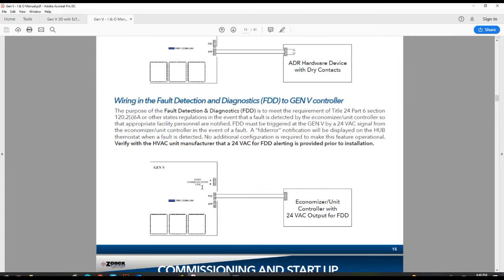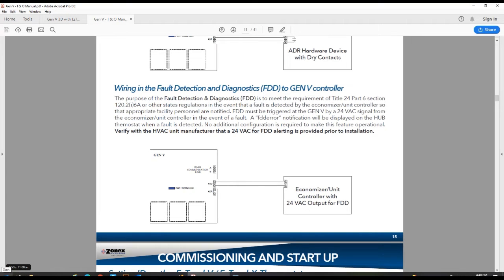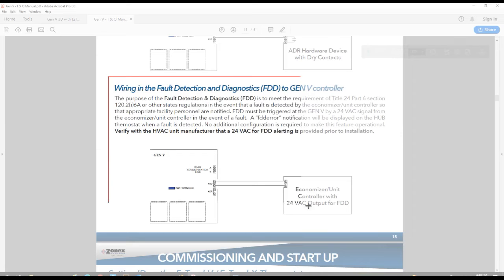We also have what's called FDD. This is the fault detection diagnostic feature. This terminal allows you to hook up an economizer to our controller that offers the FDD output or input. When your economizer has failed or there's an issue with it, it will send a signal to our controller. Then in turn, our controller will put an error message on your hub thermostat saying FDD error, and that is your indicator that your economizer needs to be serviced or looked at.